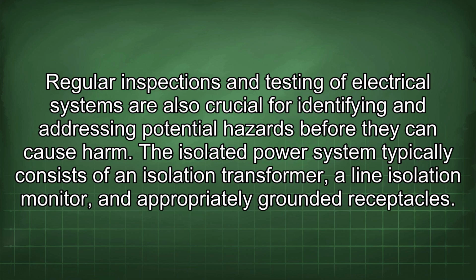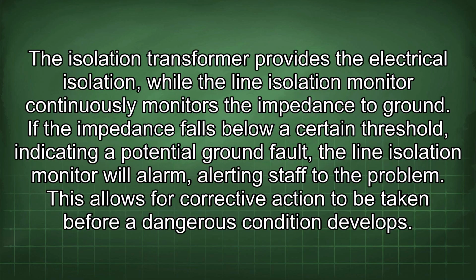The isolated power system typically consists of an isolation transformer, a line isolation monitor, and appropriately grounded receptacles. The isolation transformer provides the electrical isolation, while the line isolation monitor continuously monitors the impedance to ground. If the impedance falls below a certain threshold indicating a potential ground fault, the line isolation monitor will alarm, alerting staff to the problem. This allows for corrective action to be taken before a dangerous condition develops.